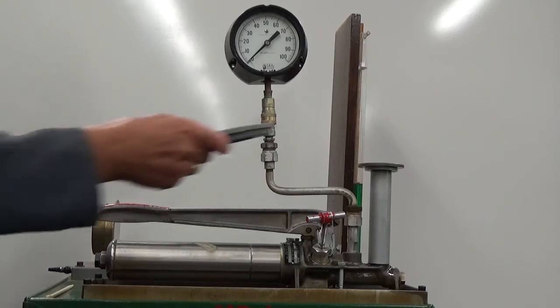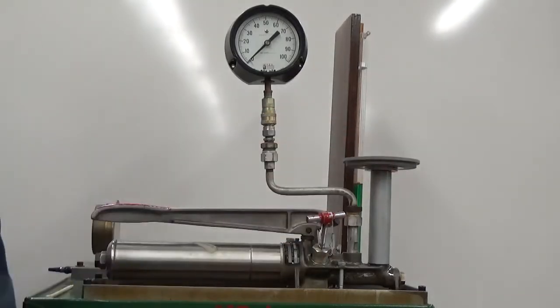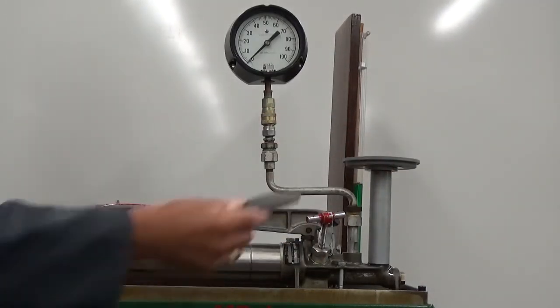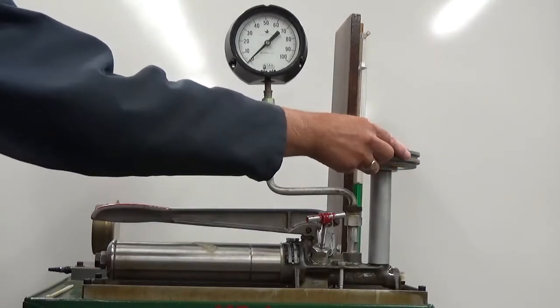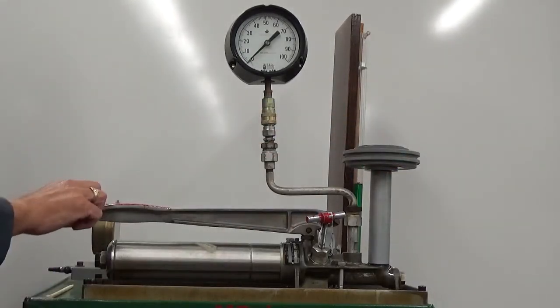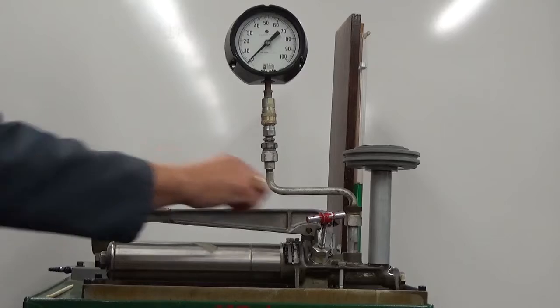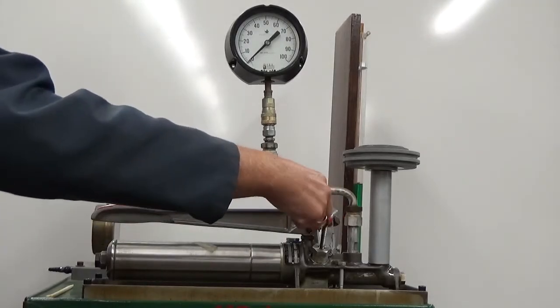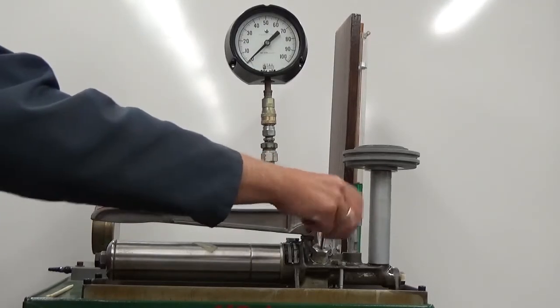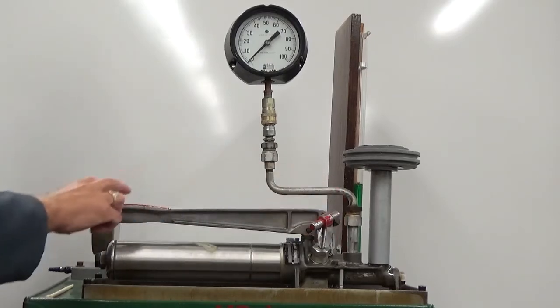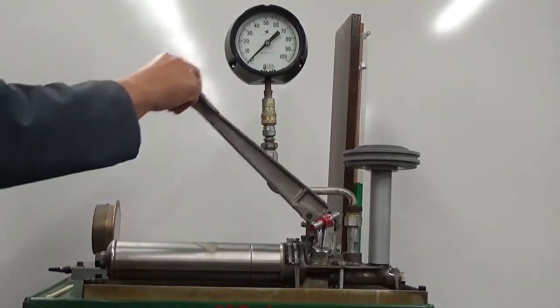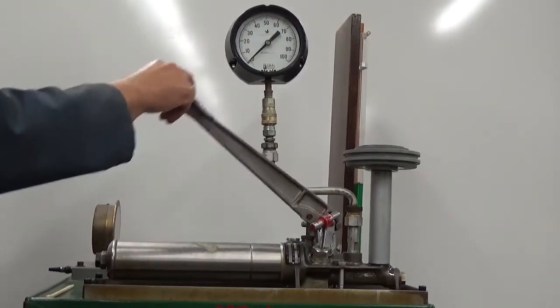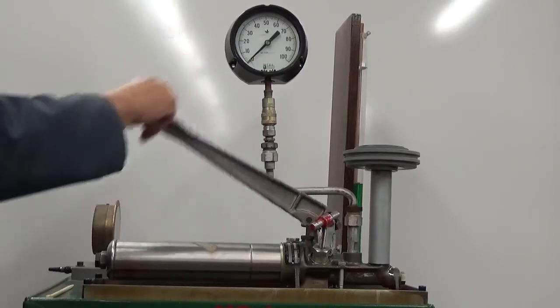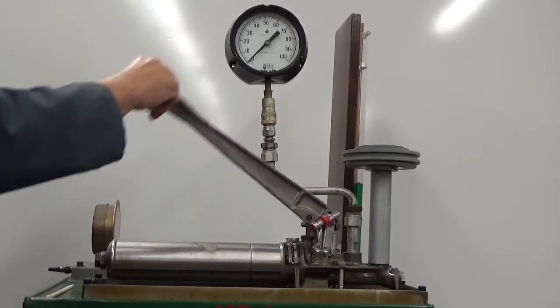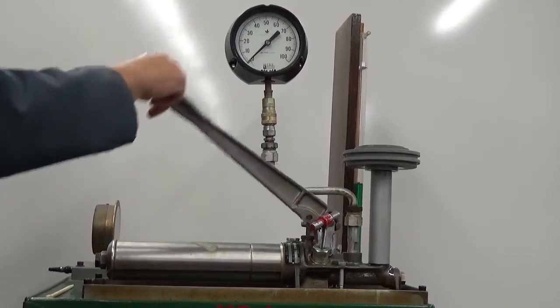To do this, we first place the calibration weights on top of the piston. So for 45 psi, we will have 2 large weights and 1 small weight. The pressure relief valve then needs to be closed to pressurize the system. Once the relief valve is closed, we can pump the system and increase the pressure on the pressure gauge. As the pressure increases, you will notice that the gauge needle starts to rise.